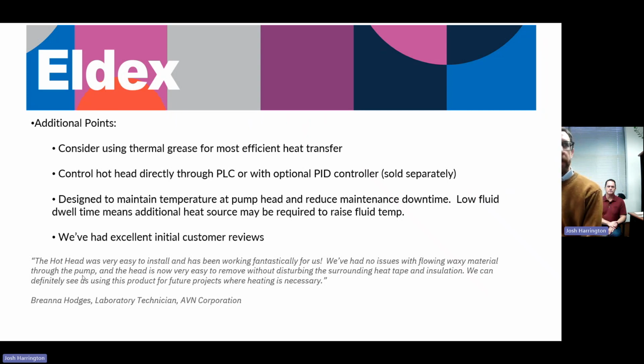As we mentioned before, the PID controller is optional. You can also control it directly through a PLC. And then another really critical point here is that this device is really designed to maintain temperature at the pump head, as opposed to raising the temperature of the fluid itself. The reason being is that there's a very low swept volume within the pump and a very low liquid dwell time, so that if you're pumping at a reasonably high rate, there's just not enough time to heat up the liquid while it's in the pump head itself. So an additional heating source may be required to raise the fluid temperature initially, and this is really designed to maintain the temperature of your system.